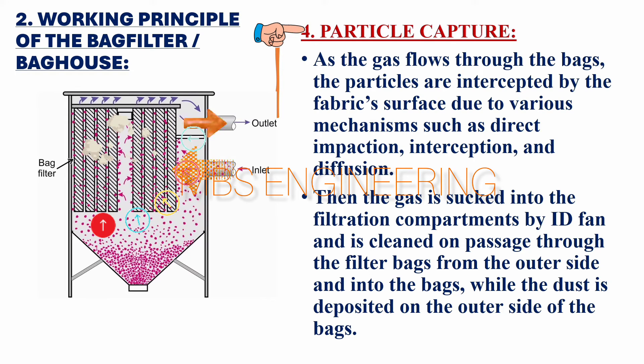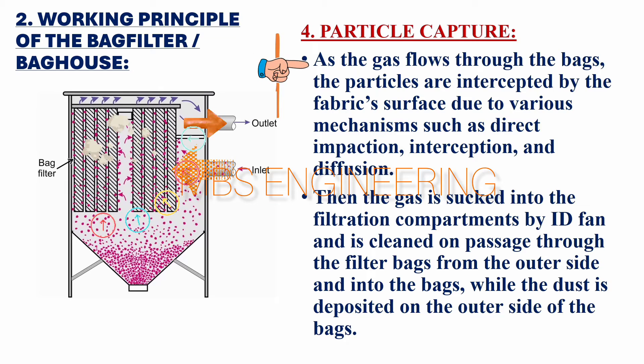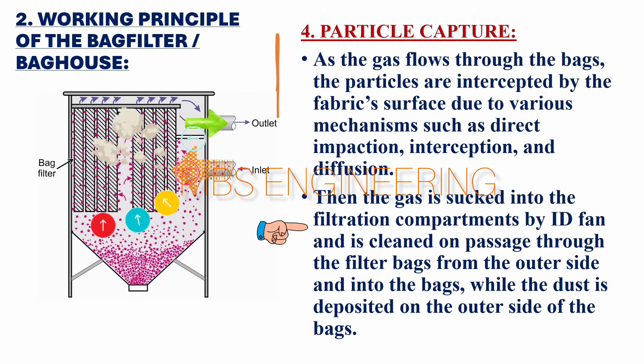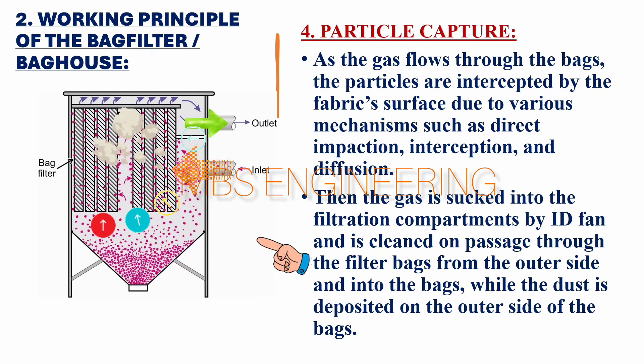Step 4 — Particle Capture: As the gas flows through the bags, particles are intercepted by the fabric surface through various mechanisms such as direct impaction, interception, and diffusion. The gas is sucked into the filtration compartments by an ID fan and is cleaned on passage through the filter bags from the outer side into the bags, while the dust is deposited on the outer side of the bags.